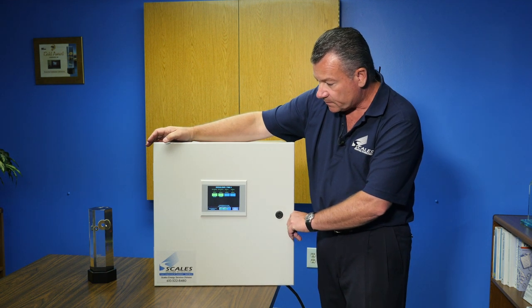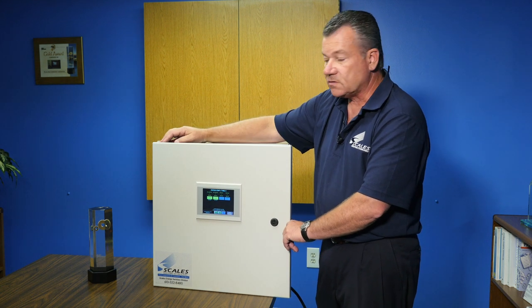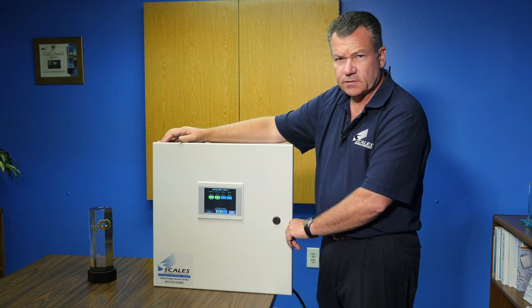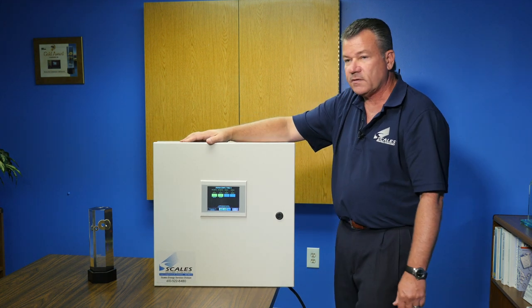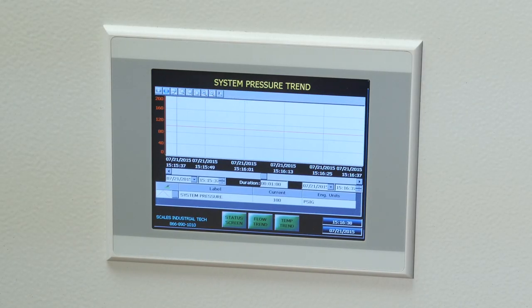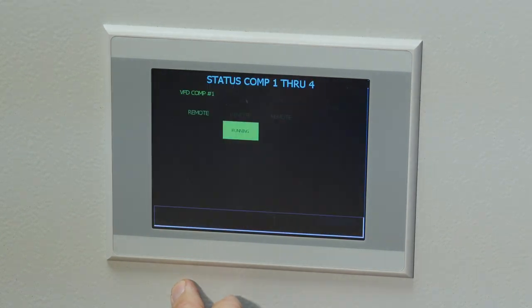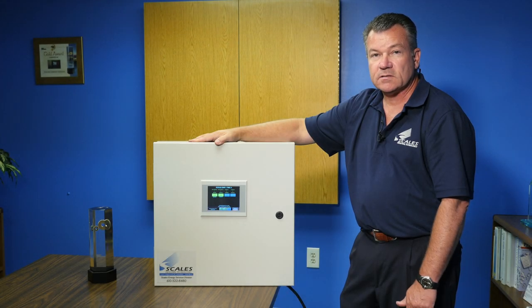There's enough information that comes on that screen for the interface and the end user to go through the status screens. There are status screens that will come up for the compressors and what sequence they are in. There's a trending status screen for both flow and for temperature, and there's also an alarm screen in case we want to hook up alarms for the air compressors.